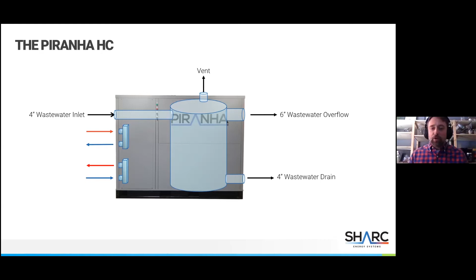Building scale wise, when we're looking at how it goes into a building, the wastewater tank there on the bottom right, as the wastewater leaves the building, it's going to go into that tank. A float system is going to maintain the level in that tank. So contrary to most tanks where you're not going to be maintaining a level, we want to maintain that usable liquid level, because that wet well is essentially our thermal battery. So as there's a call for heat in the building, the pump is going to pump wastewater into the PIRANHA. Again, it's going to fill that internal tank. We're going to use the energy in that tank, provide the domestic hot water. As that energy is used, the actuated valve here opens up and drains all the used energy out to sanitary, so we're not putting used energy back into our warm source, and then the process starts all over again.